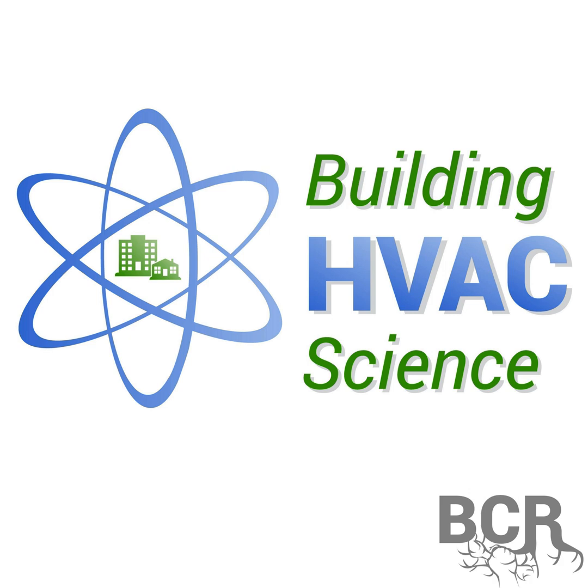We have certified Aeroseal dealers throughout 9 countries and over 700 dealers, certified to do the aerosol process, sealing from the inside out. Especially in retrofit applications, it doesn't make a difference. We can now seal an entire duct system by making one injection point down by the plenum that reaches all the ductwork behind, in attics, crawl spaces, behind walls, and finished basements.